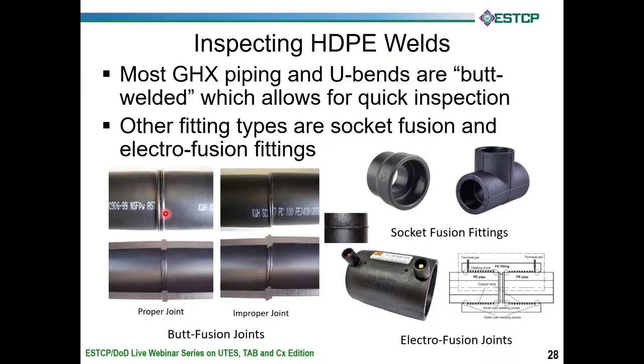And at first, I didn't like those. You look at these socket fittings, and if you've ever been involved in high pressure work like hydraulics, oftentimes you get up into thousands of psi. You have socket welded fittings. But the problem with the socket welded fittings is that you can't really see the weld visually to observe it. And we're not using x-rays or anything else to check these joints. It's more of a field inspection. So we're not a big fan of socket fusion, although you may have to do it on occasion for transitions. Really small pipe, you might have to do it.